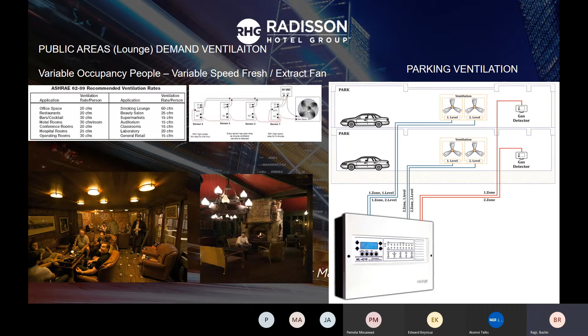Sustainability, we have to think about the third scenario of efficiency, which is variable input and variable output. The same here in a parking area, we can also install a gas detector, which is meant by quality sensor, CO and CO2. If I don't have cars running in the parking, so from the exhaust, I don't have CO or CO2, carbon monoxide or dioxide, no need to run the ventilation fan at full capacity. So the same model, this we call demand ventilation. According to the demand, I am adjusting the flow and capacity and the rotation of the fan, fresh air and the extract.